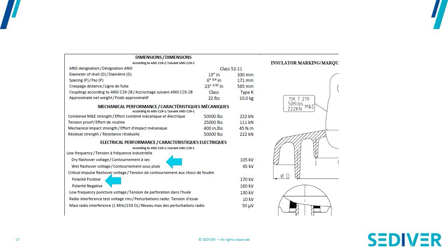When you look at a typical drawing of insulators — such as one for the Canadian market — you see several definitions under electrical performance characteristics. The first is low frequency: a 50 Hz or 60 Hz voltage applied on the insulator. The value we guarantee is either a flashover value — meaning, for example, if my insulator has a flashover of 100 kV at 50 or 60 Hz, you will see an arc at that value, but there will be no flashover below it.